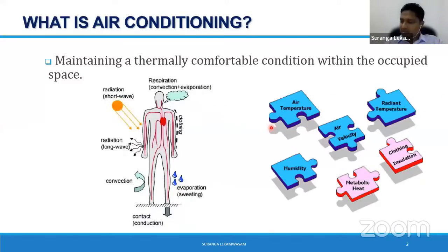There are many parameters, as I told you, which you need to maintain within a range. Air temperature is primarily an important parameter which you need to maintain. We maintain probably 24, 22, somewhere there, as we are living in a tropical climate. Then importantly, RH, or the humidity, plays a vital role, especially in countries like ours where the ambient RH is very, very high. So you need to drop the RH to a certain level to encourage moisture dissipation, or rather latent heat exchange from the human body. So again, you need to look at this in your design to control the RH.